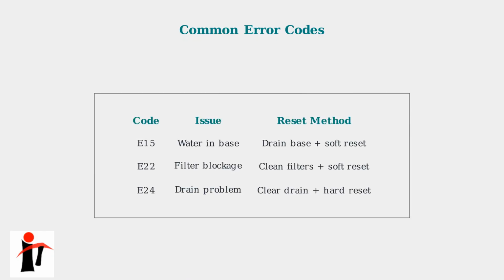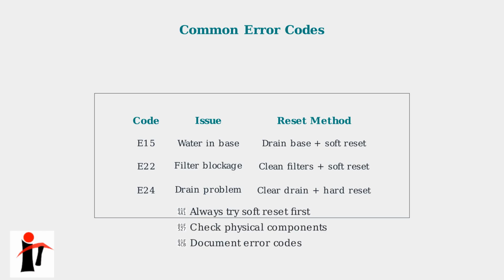Understanding common error codes can help you determine which reset method to use and whether additional troubleshooting steps are needed. Error code E15 indicates water in the base pan, which requires draining the base and checking for leaks before attempting any reset procedure. Error E22 indicates filter blockage. Clean the filters thoroughly before performing a soft reset. Error E24 suggests drainage problems. Check the drain hose and perform a hard reset if needed. Remember to always start with the simplest solution first. Most issues can be resolved with a soft reset, and only persistent problems require hard resets or emergency procedures.